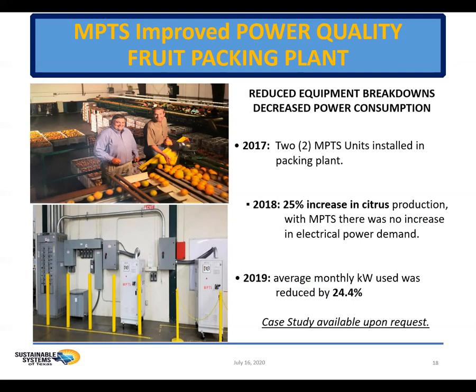PG&E, Pacific Gas and Electric, the local utility, was seeing those high reductions in kW consumed by the plant and thought that their utility meters were the problem, so they changed out the meters. And then after doing some third-party testing, they discovered that this was what was really happening. And so PG&E is currently in discussions with TransPower Company and developing a grant program for commercial and industrial users so that PG&E does not have to build additional power generation capacity in that area. The citrus plant owner is also really happy because the MPTS units that TransPower installed caught an overbilling problem that was happening, and now PG&E and the citrus plant are in discussions on how to fix that problem.